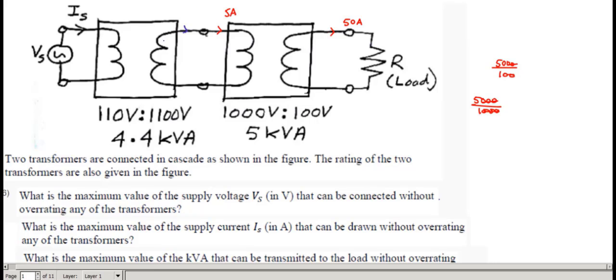Now how much current flows in the secondary of the first transformer? 4.4 kVA divided by 1100 gives 4 amperes, so 4 amperes is flowing here. Similarly, 4.4 kVA divided by 110 gives 40 amperes flowing here.